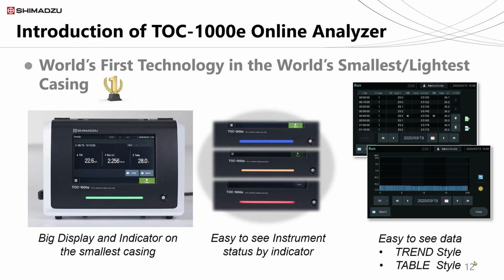As you can see on the slide, TOC-1000e has a big, colorful LCD touch panel screen. You can see the values on the screen easily. Also, there is a LED bar indicator on the bottom of the front door. It has 4 different colors and each color gives us information about the situation of the instrument. Blue means running, green is ready to start measurement, orange color is warning and not ready for measurement yet, red color tells us that there is an error on the system and it needs to be checked immediately.